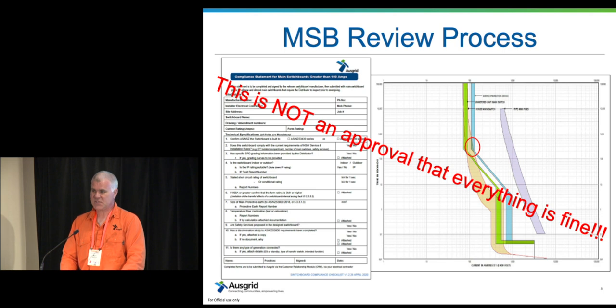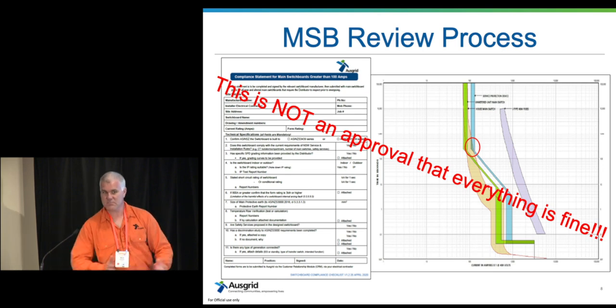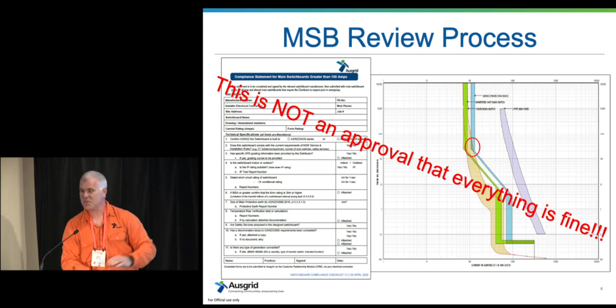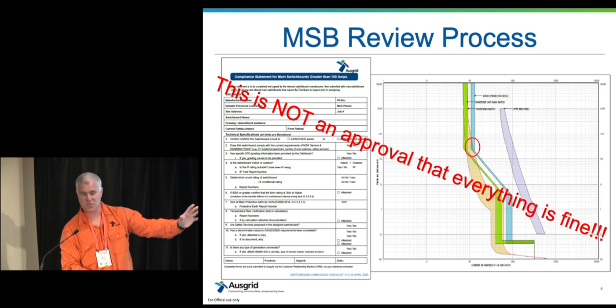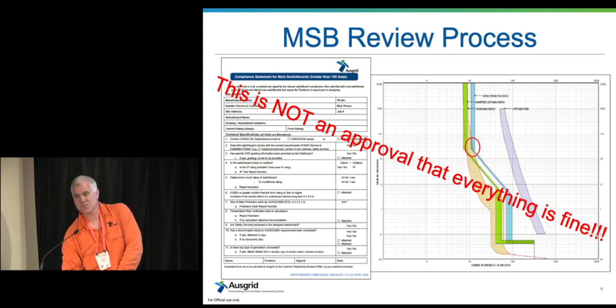Because worst case scenario, if your switchboard does not discriminate, Ausgrid's protection will likely set off, but you might be turning off a few buildings next to the site that you're on. And we'll just stand back and go, that's their problem, guys, go recover the costs off them, because they're the ones that have not installed a correct switchboard. So you need to make sure that discrimination is correct.